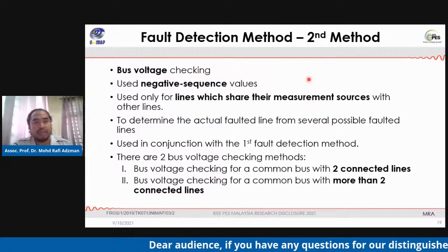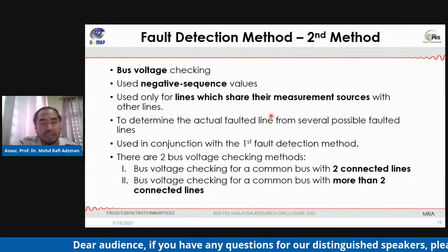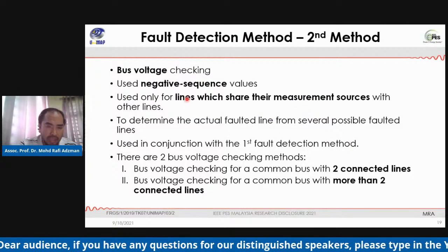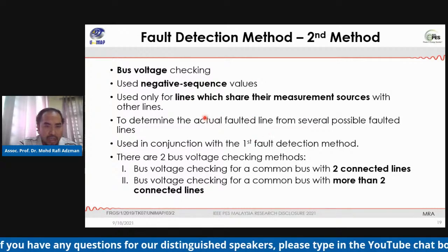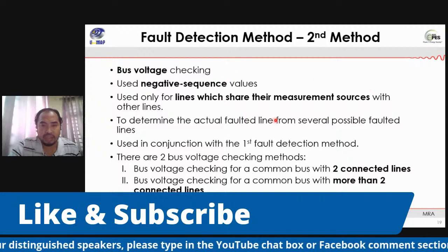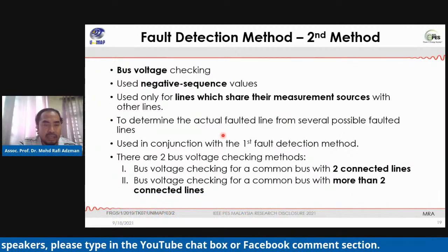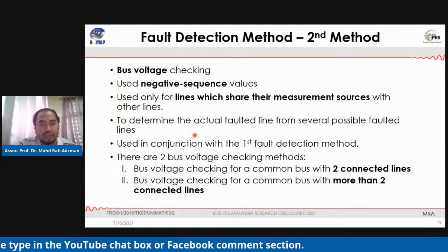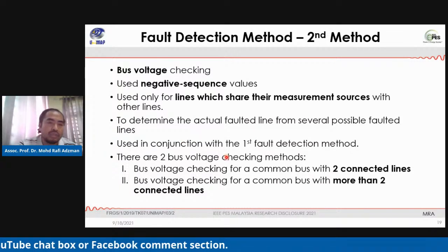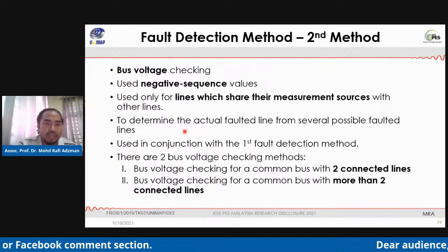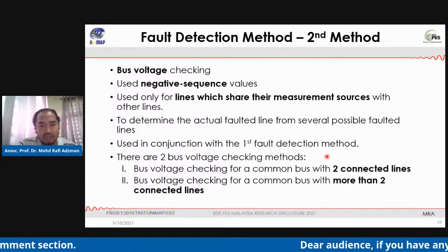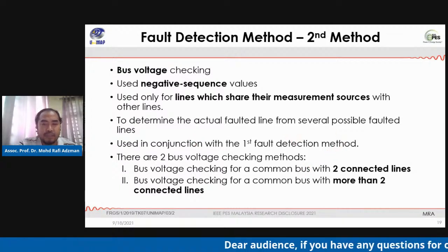For the second method, we use bus voltage checking. We use negative sequence values, and use it only for lines with a shared measurement source with other lines, to determine the actual faulted line from the several possible faulted lines. This method is used in conjunction with the first fault detection method.